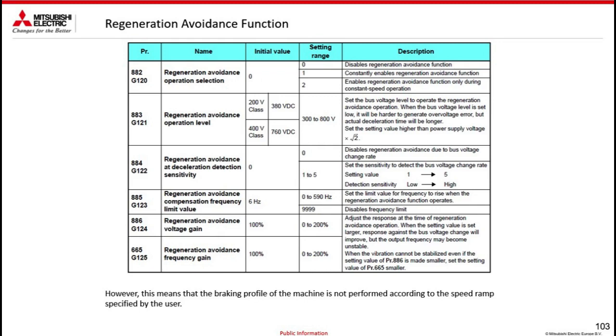These are the thresholds for the intervention. You can vary them to make it intervene earlier and so on. The parameter 884 is the sensitivity with which it must respond. So I vary the value of this parameter to have a lower sensitivity rather than a high one. The parameter 885 defines the maximum frequency that can be delivered as compensation. So I said take a little more frequency, okay, but how much? By default, it's limited to 6 Hz. If you want, you can go even higher.